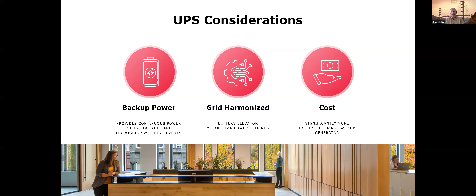For really large high-rise systems, I think the cost of the UPS system may be prohibitive, but some of the other technologies that Jeff and Harvey were talking about earlier in the presentation help to reduce the peak demands of the elevator, and that would make a UPS that much more cost viable, but still likely to be more expensive upfront than your generator. But the maintenance requirements of your UPS on a weekly, daily basis are greatly reduced. There is the need to replace the batteries in your UPS once every 10 to 15 years, depending on the usage of the system.